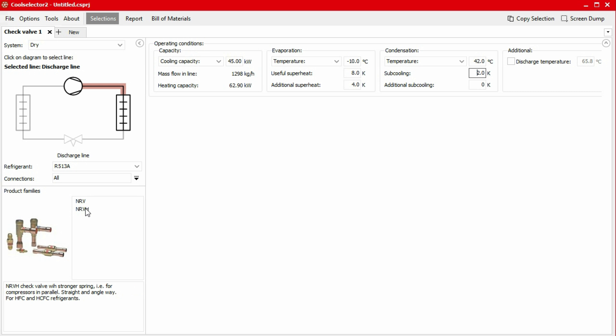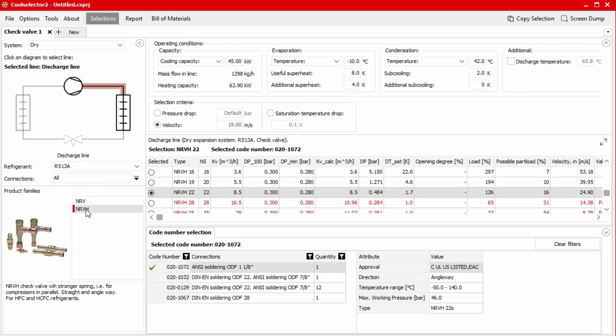These are almost identical products except that the NRV-H has a stronger spring to provide a tighter seal on the port. The NRV valve has standard strength springs, while the NRV-H check valves are equipped with a stronger spring to form a tight seal and protect against refrigerant flowing back from the discharge line and into the cylinders of the compressor. When reciprocating compressors are used in parallel or in a power pack, they will generate a lot of pressure pulsation — this is where the NRV-H valve should be used. Furthermore, to avoid piston oscillation, partially open check valves in the discharge line should be avoided. For this example, we'll assume parallel reciprocating compressors are used and therefore choose the NRV-H valves.